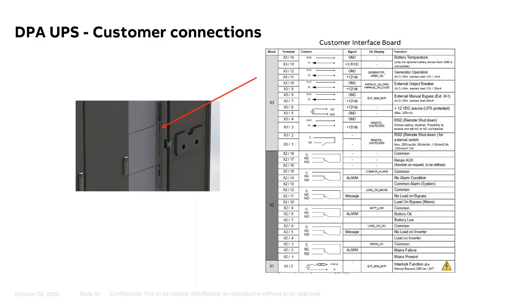The UPSs come standard with a communication board like that. Over the years, things have been added, like signals from a generator if we want to limit battery charging while on generator. What you would expect from any modern UPS today. On that note, as I mentioned earlier, the majority of UPSs in the market are now IGBT rectifier and inverter, double conversion, power factor corrected input, unity rated power factor. So a 500 kVA will support 500 kW. That's true across the board. And the efficiency, even if the modular UPSs are based on smaller power modules, for the 500 is still around the same as a monolithic, pretty much like any similar sized UPS in the market.